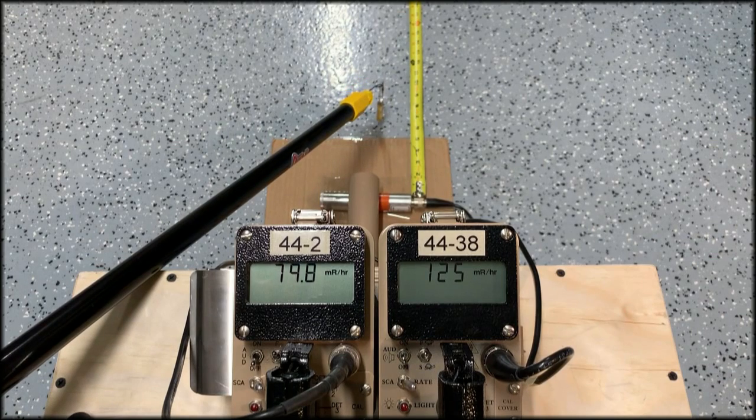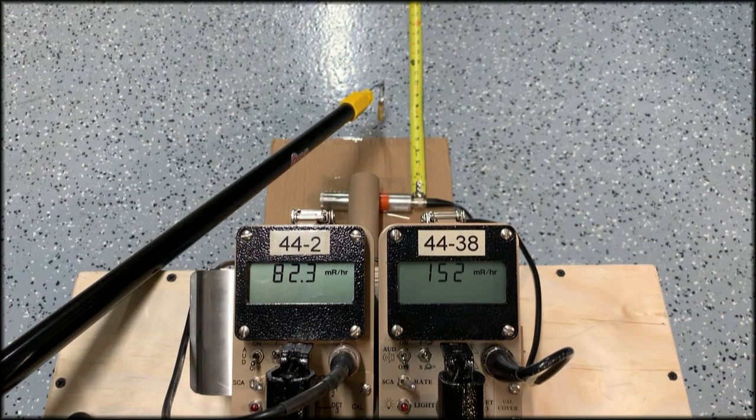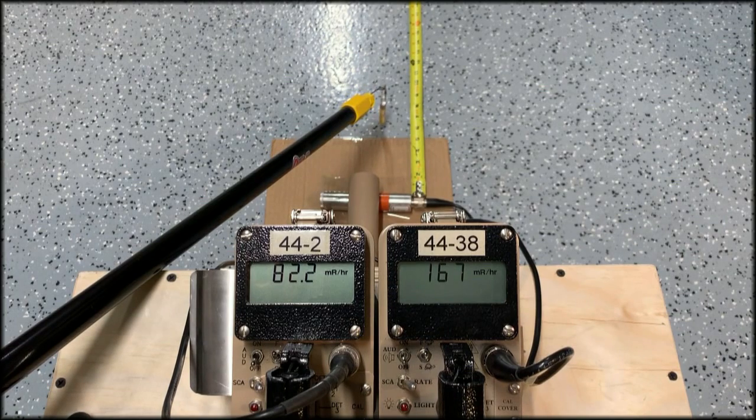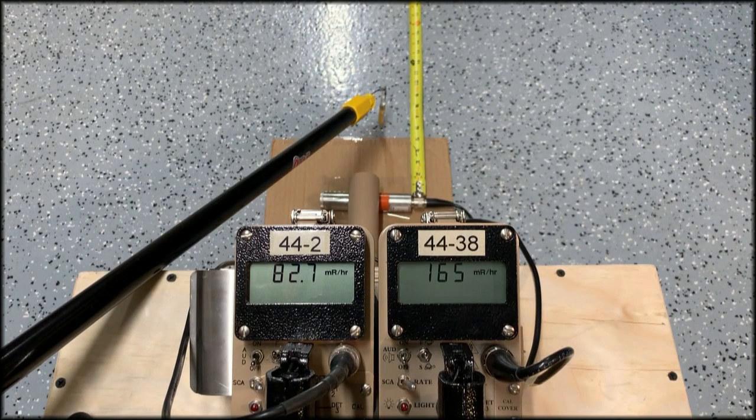Now I'm about six inches away. And what you see here is where you could kind of run into a problem. I'm in a 160 mR per hour field. And my Ludlum 44-2 detector is only telling me it's a little over 80 mR per hour.